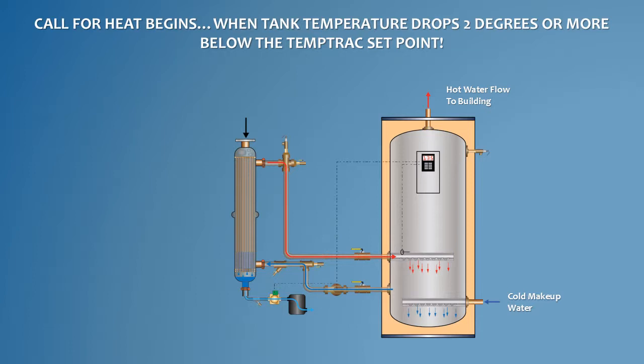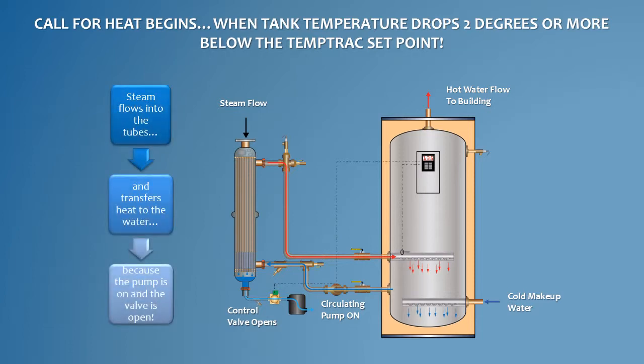When enough cold water enters the storage tank to lower the tank temperature 2 degrees or more below the TempTrack set point, the control energizes the circulating pump between the tank and heat exchanger and opens the condensate control valve. As the pump circulates, the cold domestic water from the storage tank enters the shell side of the heat exchanger and extracts heat from the steam, causing the steam in the tubes to condense. This creates a pressure drop in the steam inlet piping, which allows additional steam to enter the heat exchanger to heat the circulating domestic water before it returns to the storage tank. The condensing steam in the heat exchanger tubes flows through the condensate control valve into the main steam trap and out into the building condensate return system.